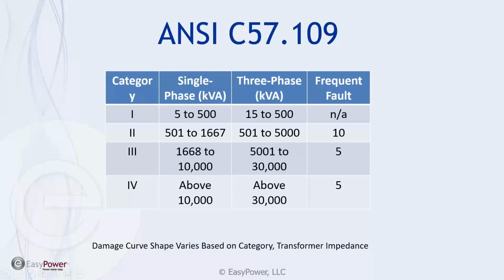And so there are tables and plots in ANSI C57.109 similar to this, where it gives us a definition of certain categories, both for single phase and three phase, and then different size ratings, and then whether or not they are subject to, or should be considering, frequent faults. This will make more sense when we see the TCC curve. But basically on the larger transformers, the susceptibility to frequent faults is more significant, and consequently they're only allowed 5 frequent faults during the life of a transformer, whereas a category 2 could potentially survive 10 frequent faults over its life.